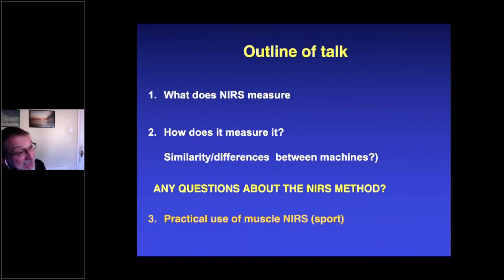measured the fat layer and then used that as part of his correction. Because if you measure light at 980 nanometers, you get a direct measurement from the fat. So you can actually use the same device to measure the fat itself for that individual at that site and then correct that way. I think it's more complicated, so it's a more difficult device to use, but that would be my way forward.